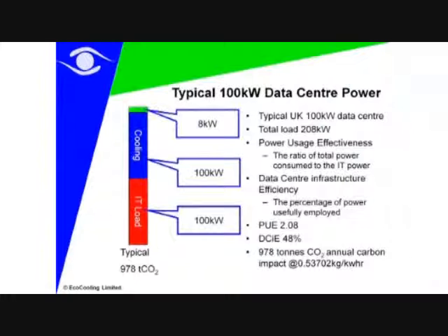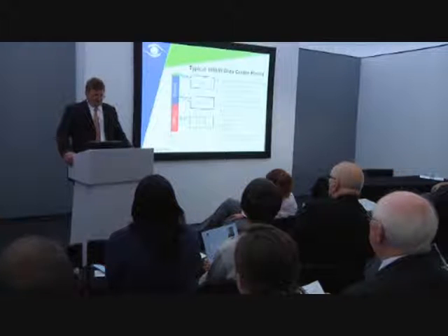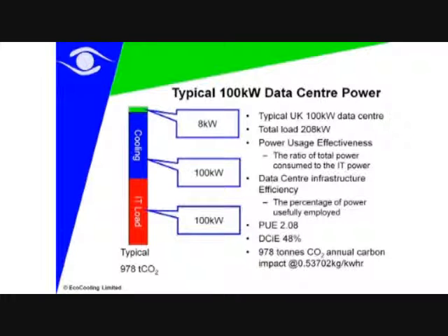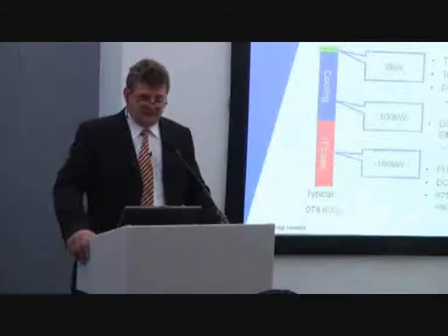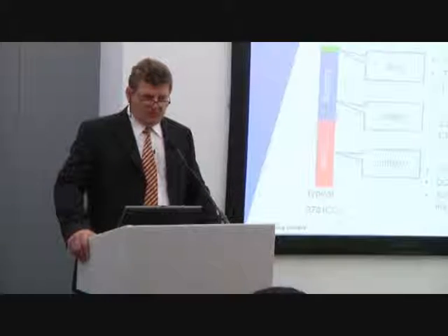What we call a PUE, a power utilization effectiveness. Now, what do we mean by PUE? Very, very important concept. We look at an efficiency of a data center and its energy use, or a server room, by looking at the ratio between the total energy used against what's really useful work done in the IT equipment. Now, many data centers in Britain run at a PUE of anything up to 2.5. Now, the only way you can get to using more energy in your ancillary equipment than in your IT equipment is really by putting it into the cooling equipment. Many people are absorbing as much energy in their cooling as they are in their IT.